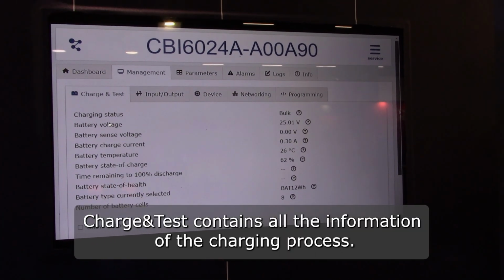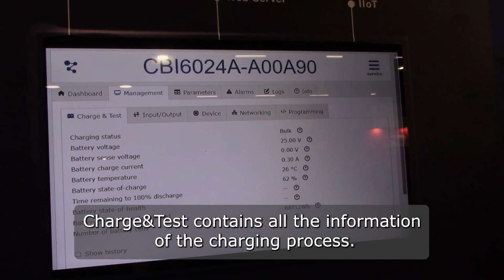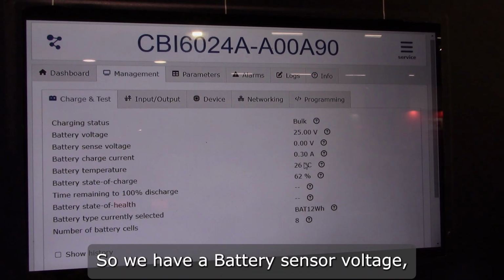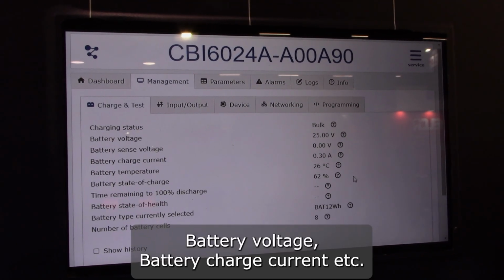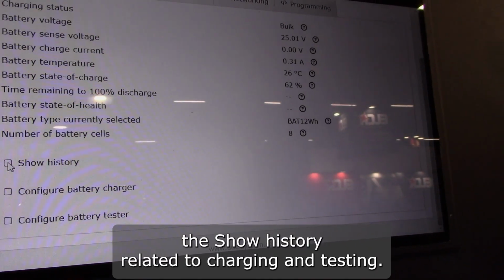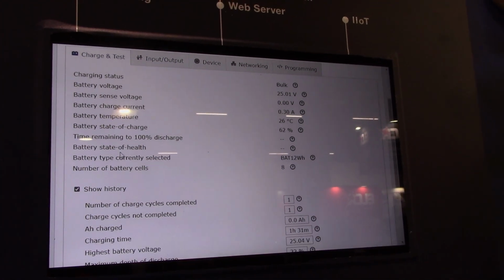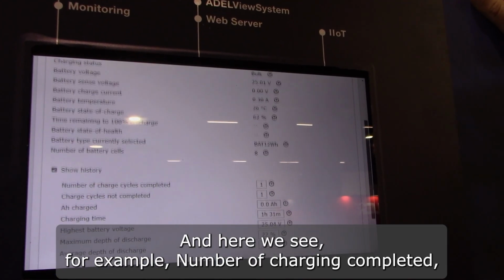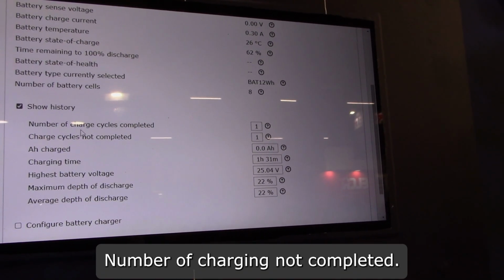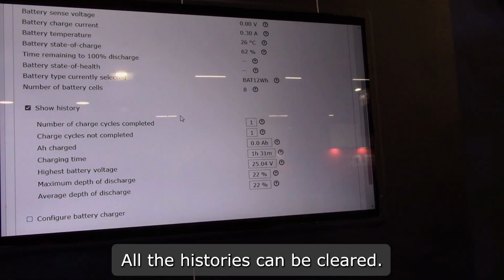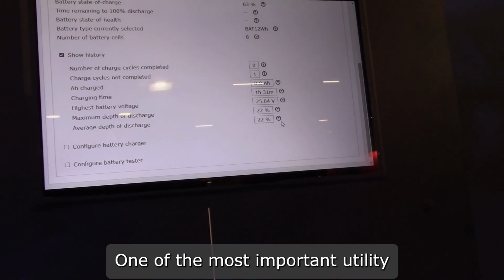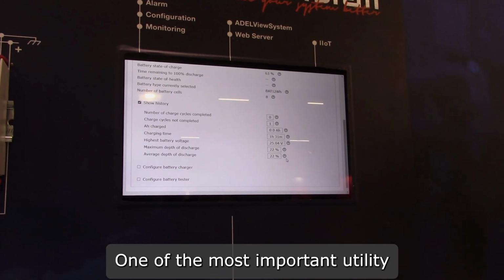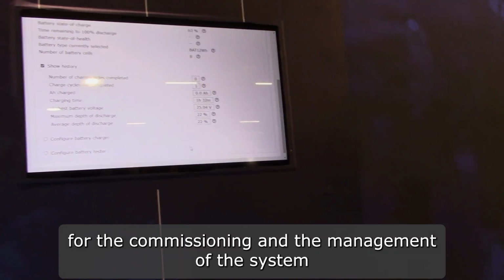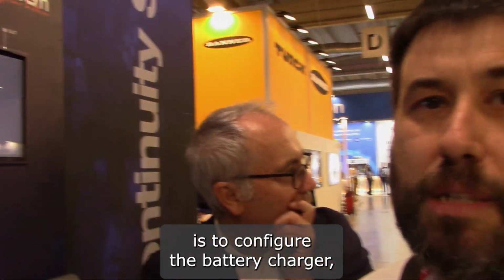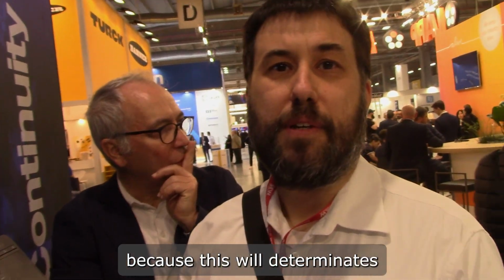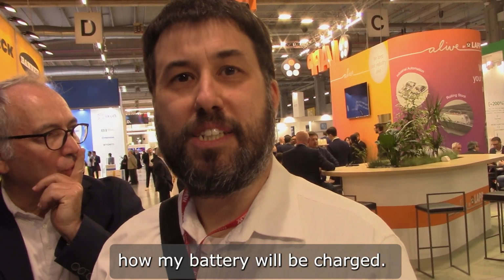Charge and test contains all the information on the charging process. So we have battery sense voltage, battery charging current, and so on. The history related to charging and testing. And here we see, for example, number of charging completed, number of charging not completed. All the histories can be cleared. One of the most important activities for the commissioning and the management of the system is to configure the battery charger, because this will determine how my battery will be charged.